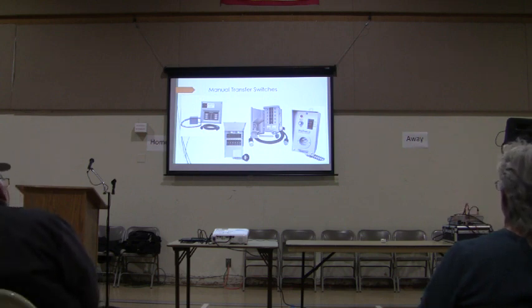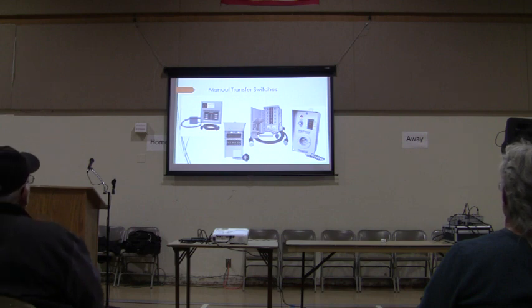Generally speaking, for a generator 5,000 watts and under, 6 circuits. Over 5,000 watts, 10 circuits. And you can see what they look like here, and they all have circuit breakers built in. Many of them have watt meters, so you can see what your load is. This one here is a little different. This is a dedicated furnace transfer switch. These typically are installed by an electrician.